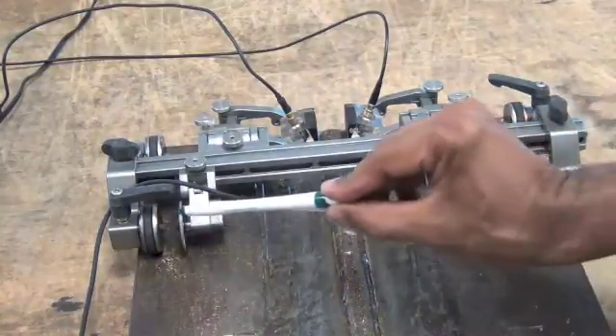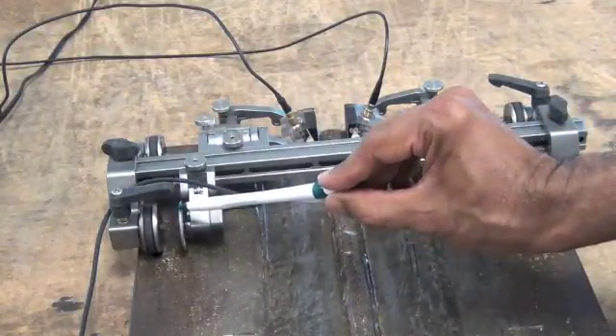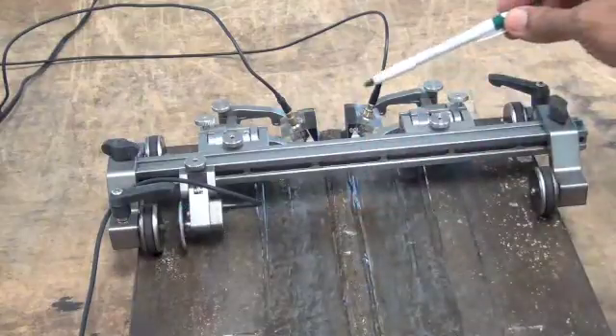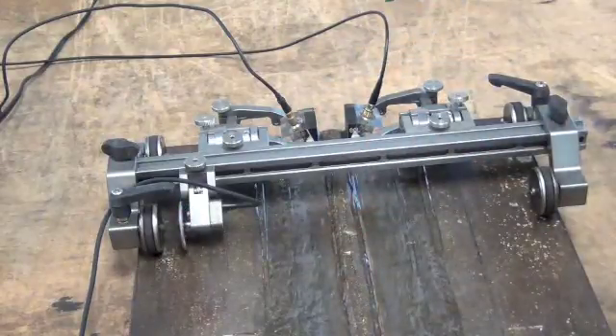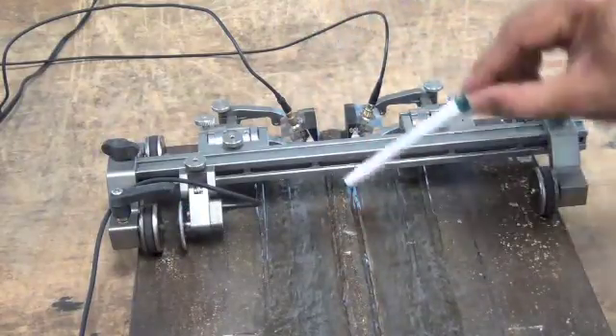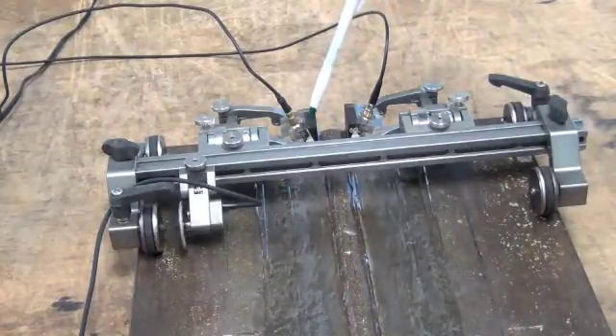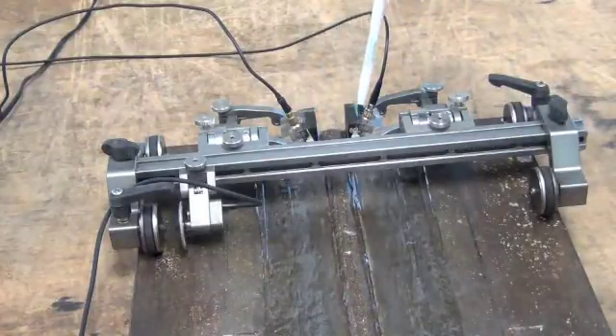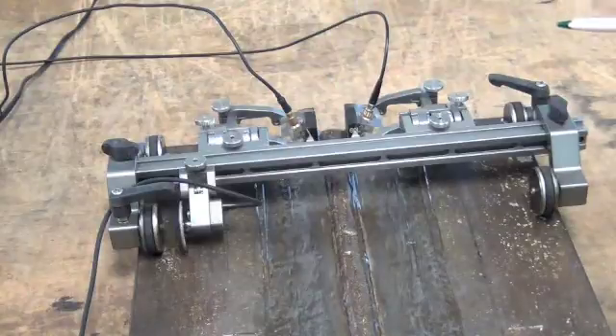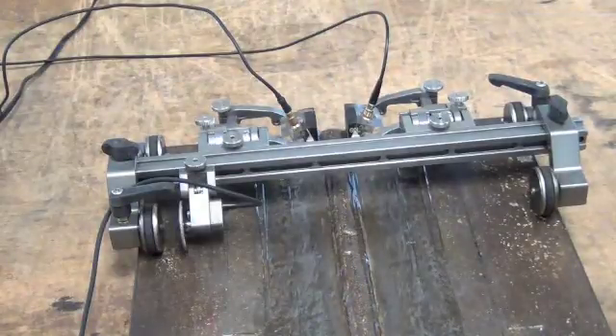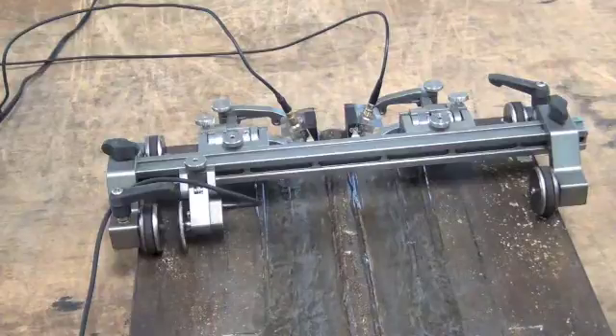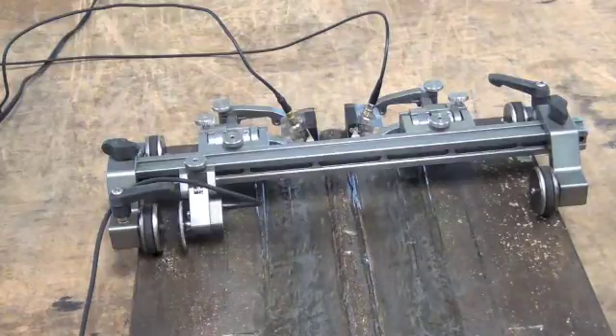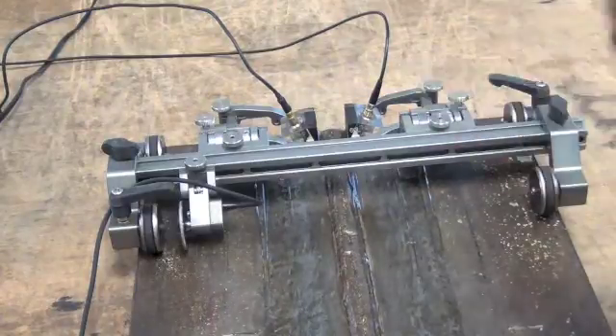Here is the encoder which takes the position reading and these are the two TOFD probes. As you can see, the weld cap is right here and we have placed the probes as close as possible to the cap to minimize the PCS distance. Now I will scan the weld and you will see the response on the OmniScan.